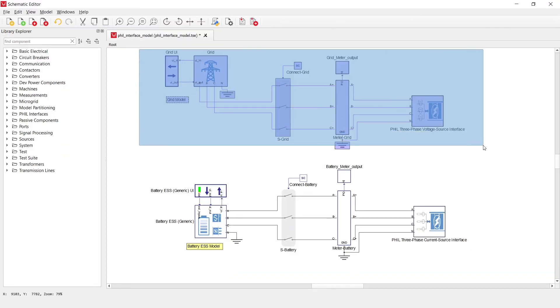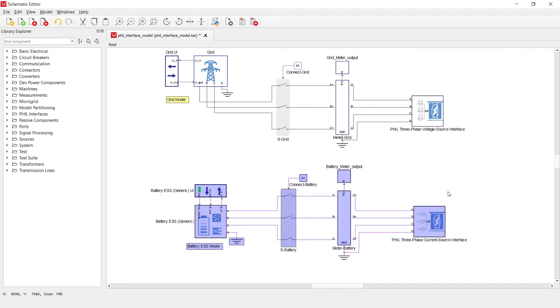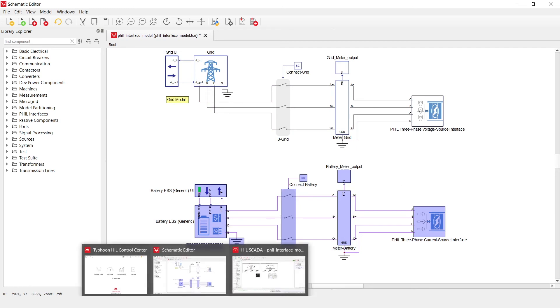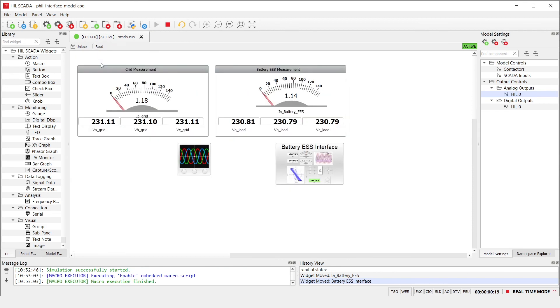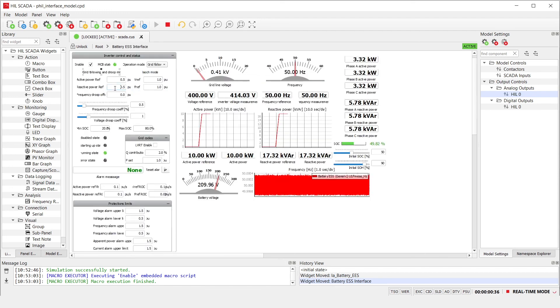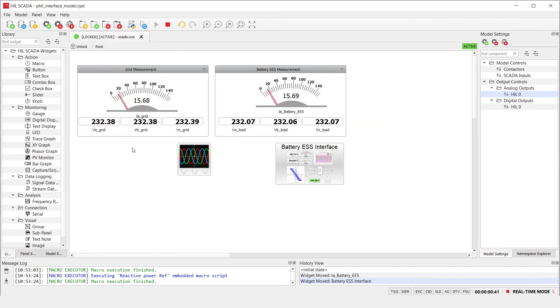In the simulation, the grid part of the model and the battery part of the model will exchange data through the HIL input/output interface. Next we will start the simulation. Here we have grid side measurements — phase voltage is around 230 volts for the situation when the battery is turned off. Next we navigate to the battery interface and turn on the battery. Now the battery supports the grid and we can see that the voltages on the grid side have increased. We then navigate to the battery interface and change the reactive power reference for the battery. We can observe that the current on the grid side and on the battery side are the same, while the grid voltage measurements show a slight decrease in value.